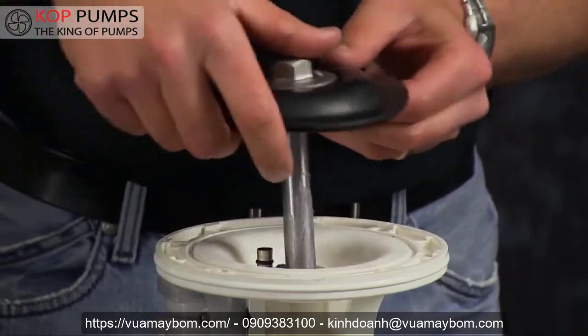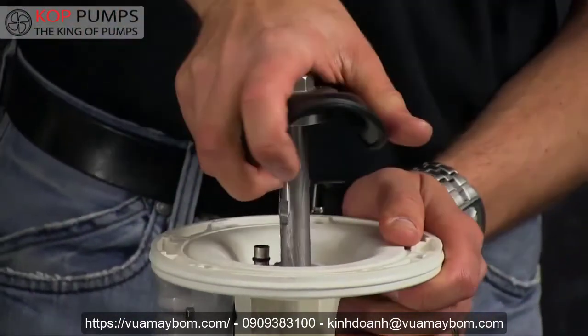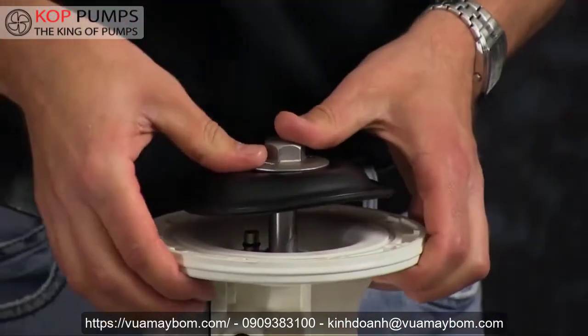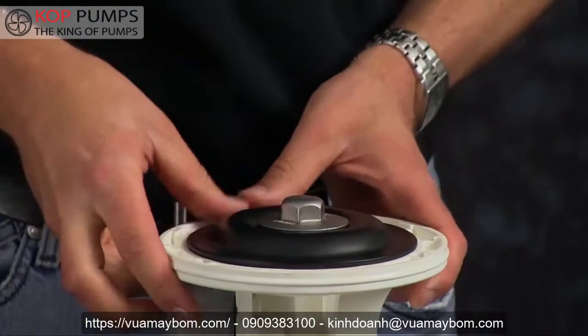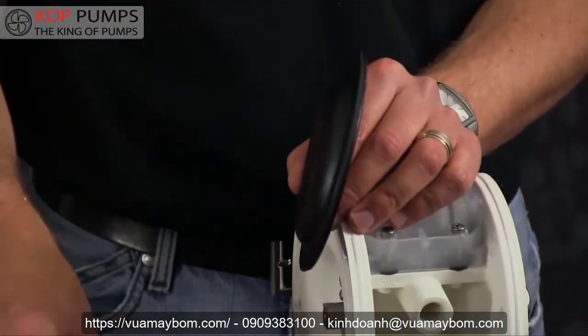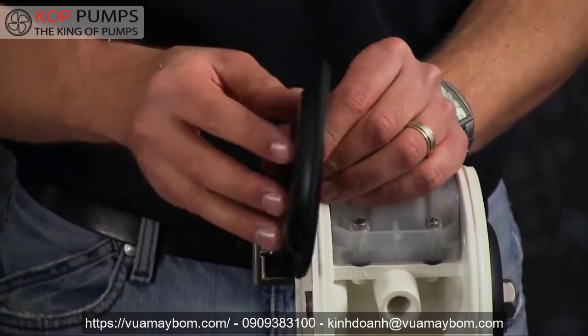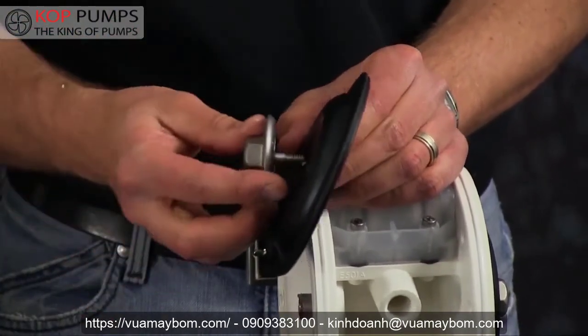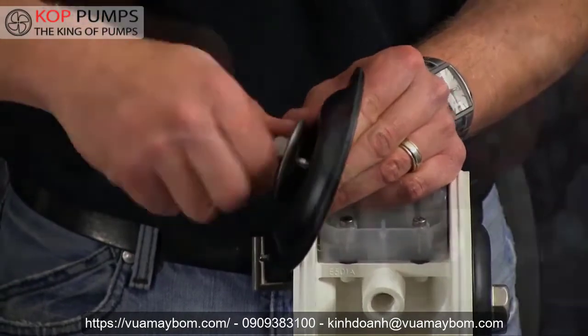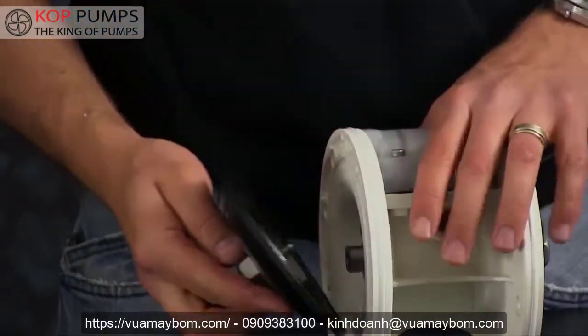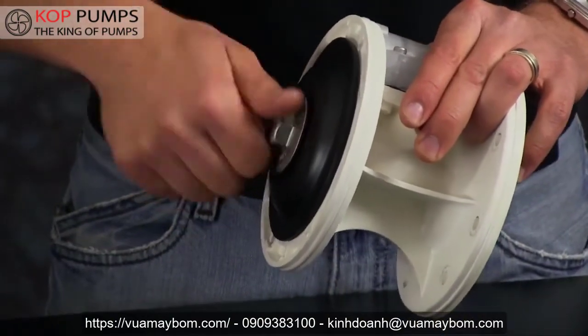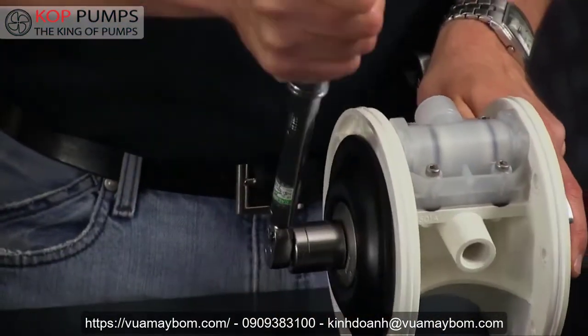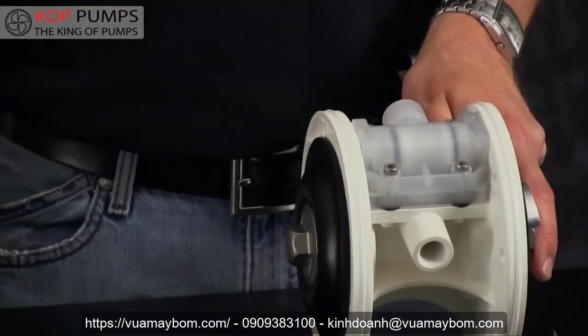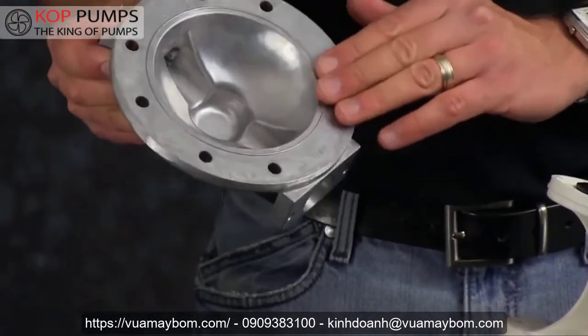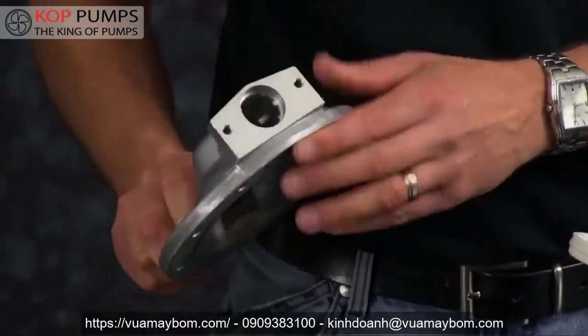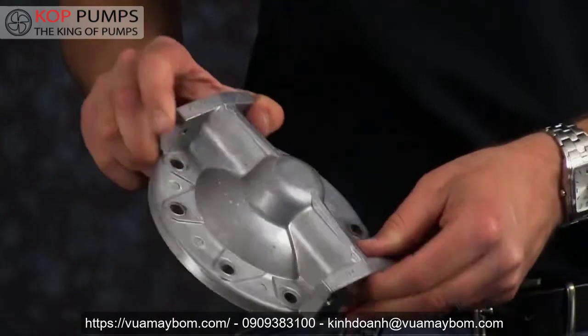Insert the rod and properly seat the outer bead of the diaphragm into the accepted groove of the intermediate. Be sure that the outer bead of the diaphragm seats properly into the accepted groove in the intermediate of the pump. Torque the opposite side to the rod. Inspect the outer chamber for casting integrity.